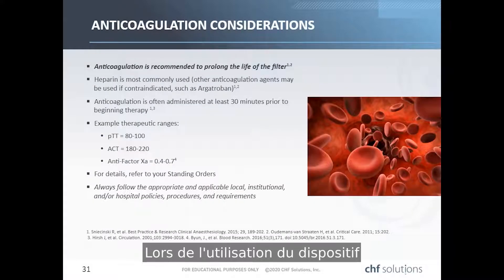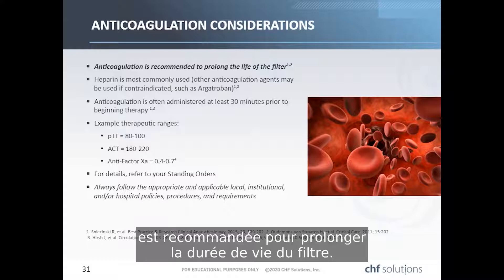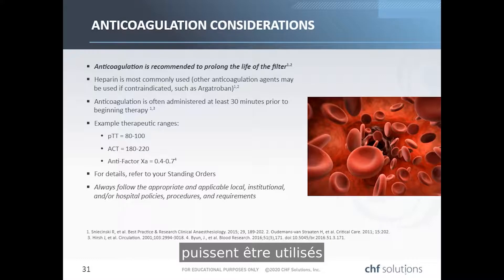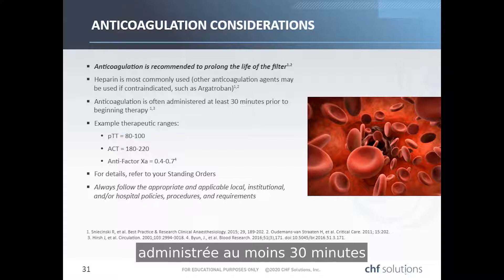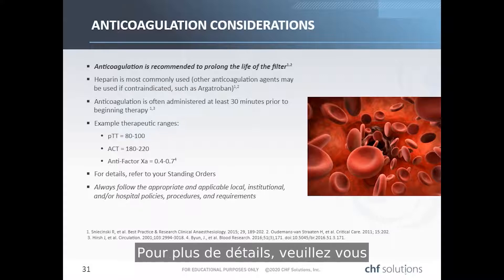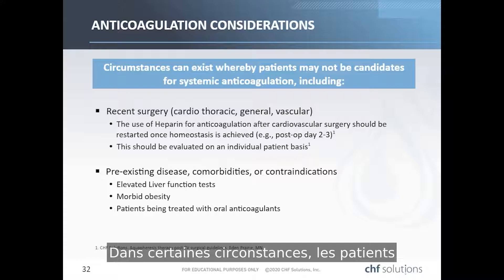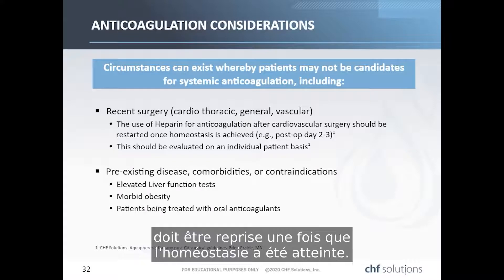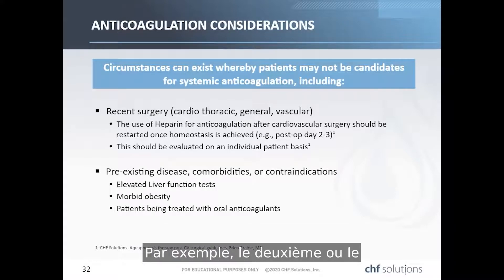When utilizing the Aquadex device, anticoagulation is recommended to prolong filter life. Heparin is the most commonly used therapy, although alternatives such as argatroban may be used if heparin is contraindicated. Anticoagulation is often administered at least 30 minutes prior to beginning therapy. There may be circumstances where patients are not candidates for systemic anticoagulation, such as recent cardiothoracic surgery. In that case, heparin should be restarted once hemostasis has been achieved—for example, post-op day two or three—evaluated on an individual patient basis.